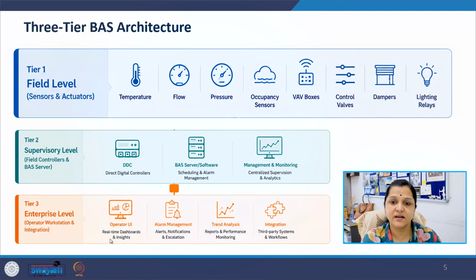The second tier is the supervisory level. This includes direct digital controllers and building automation servers. Controllers process field information locally, while the building automation servers manage scheduling, alarms, and system-wide coordination. The third tier is the enterprise level. This includes operators, workstations, graphical interfaces, floor plans, trend graphs, and integration gateways. Each tier performs a distinct role, but all tiers operate together as part of a unified control system. This three-tier structure improves scalability and allows buildings to manage complex operations effectively.